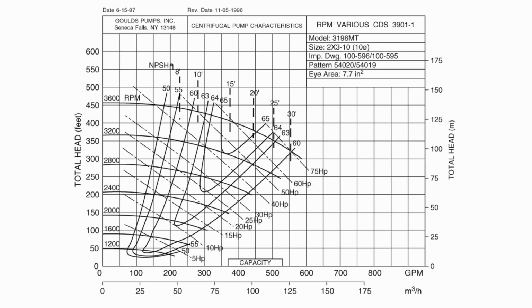All right, so let's look at this figure. This is one of those manufacturer-provided visual representations of pump performance. So here's a pump performance curve. It's got a lot of stuff on there. It looks like just a bunch of chicken scratch at first glance. But this is actually showing both traditional units on the left axis and SI units on the right axis. Here on the x-axis, we've got flow rate in both cubic meters per hour and gallons per minute.